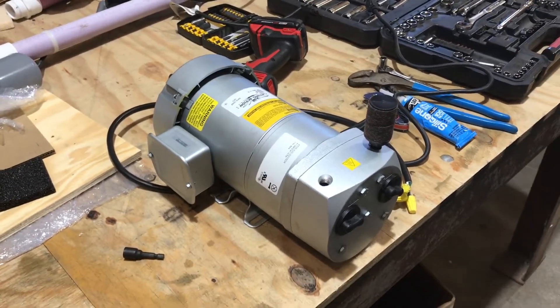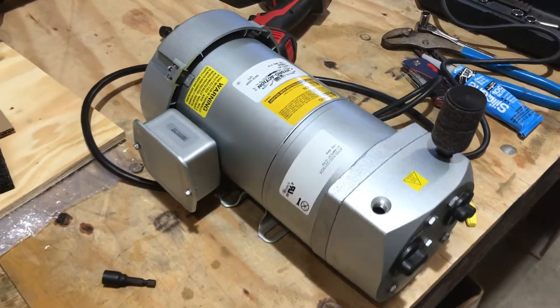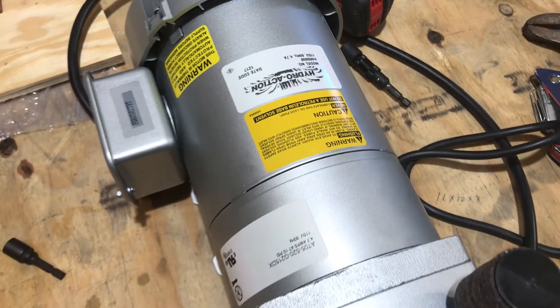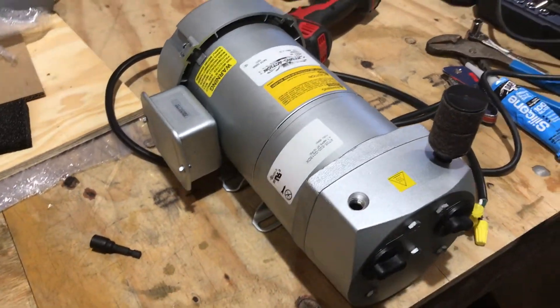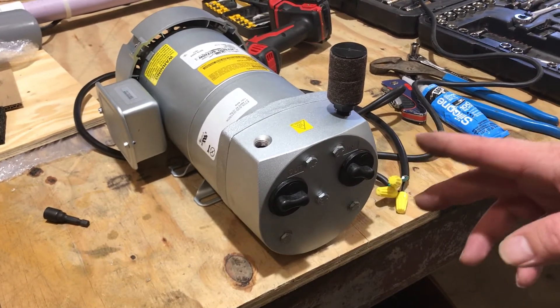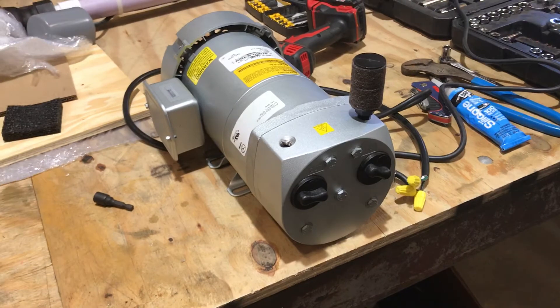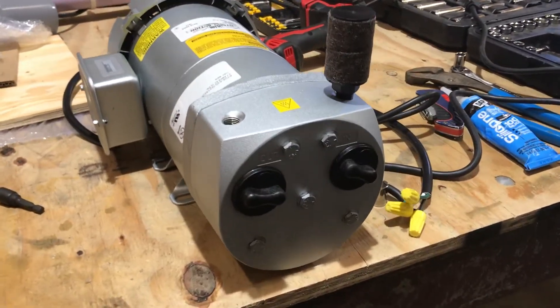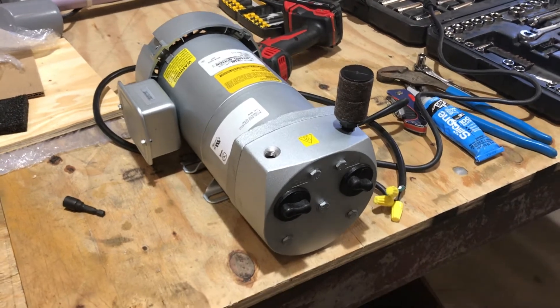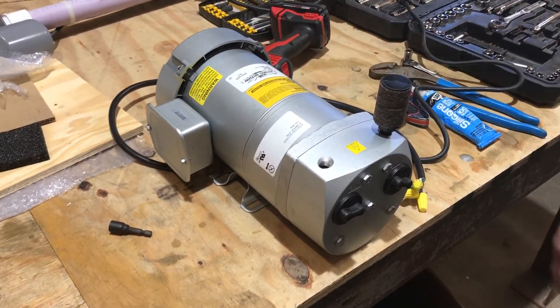That's how you rebuild a rotary vane compressor. They're all basically the same — Gast, Thomas, they're all going to be exactly the same putting them back together. As far as spraying stuff on the inside where the rotor is, you don't need to do that — we've never done it. Just clean it out real good with a rag, make sure there's no carbon bits in there, and whip it back together. And like I said, the orange gasket on the inside — if it's on there, just leave it on there.